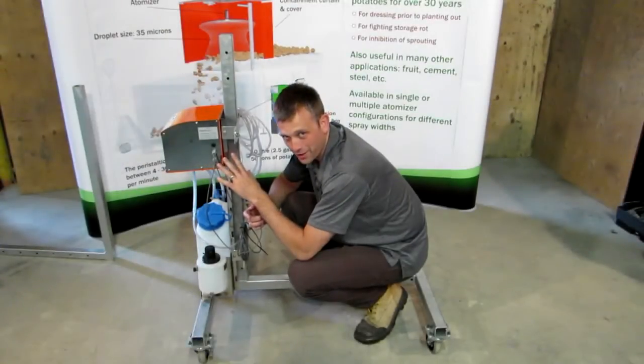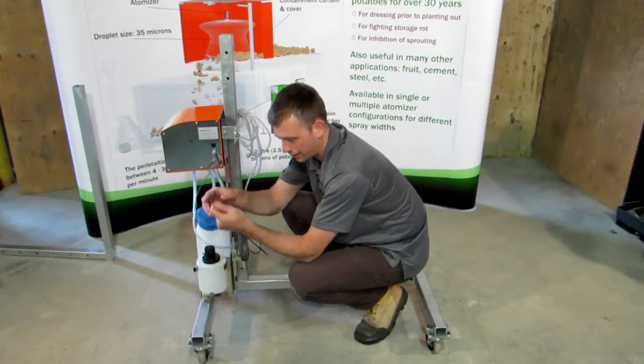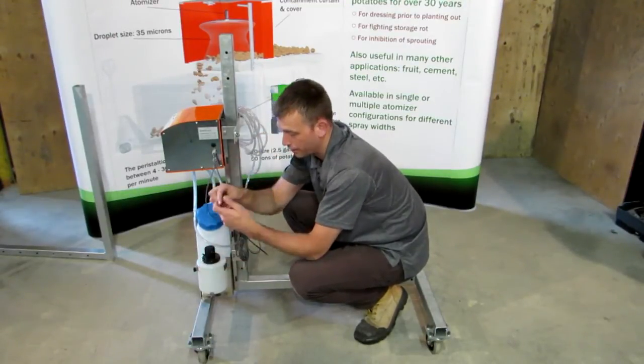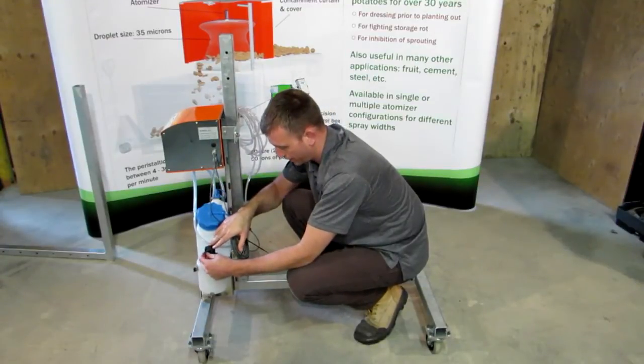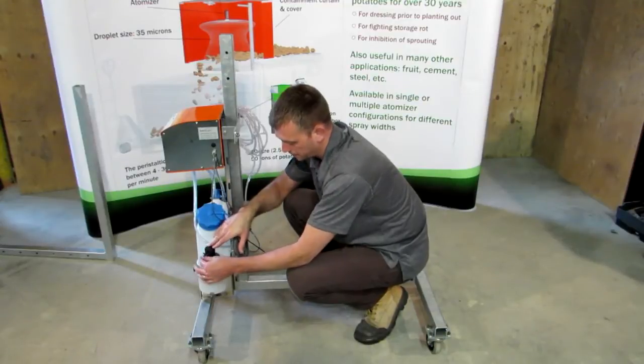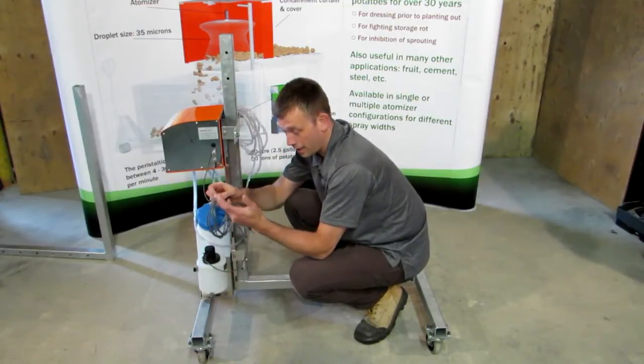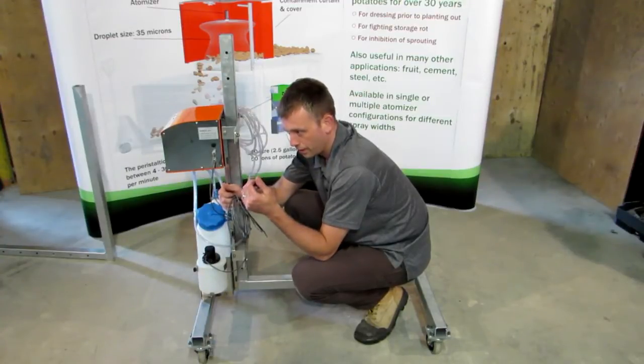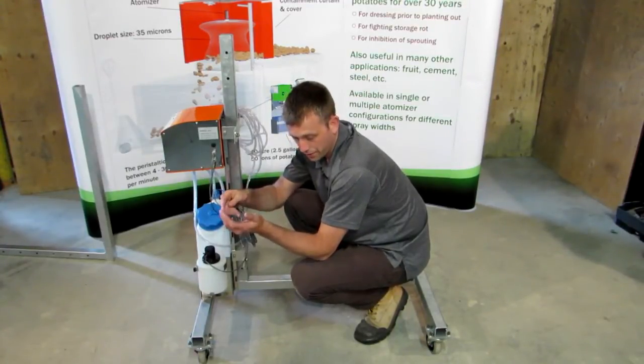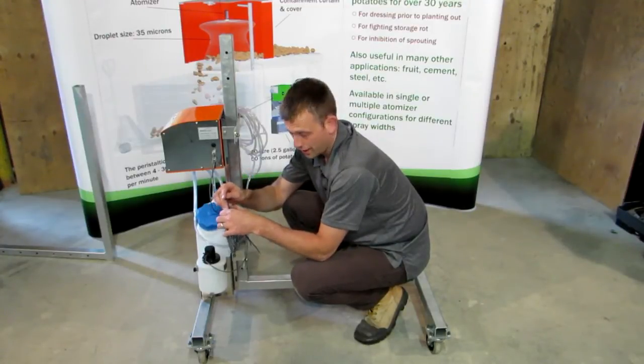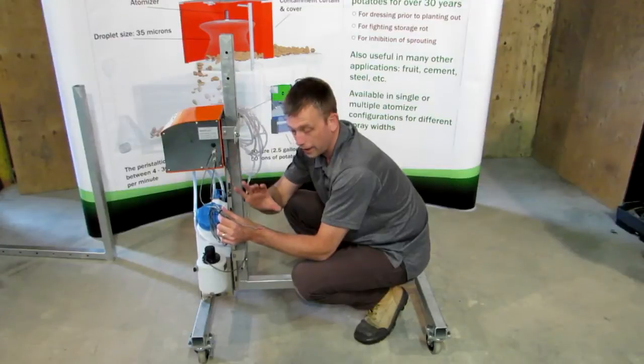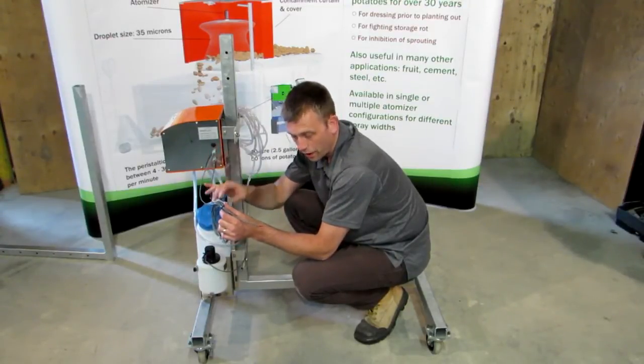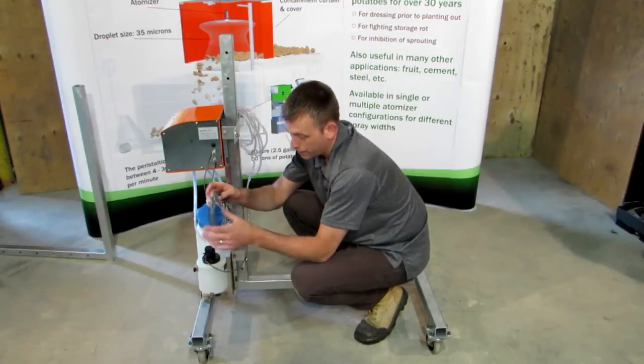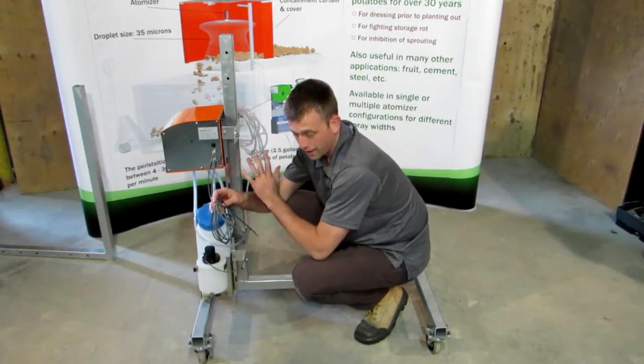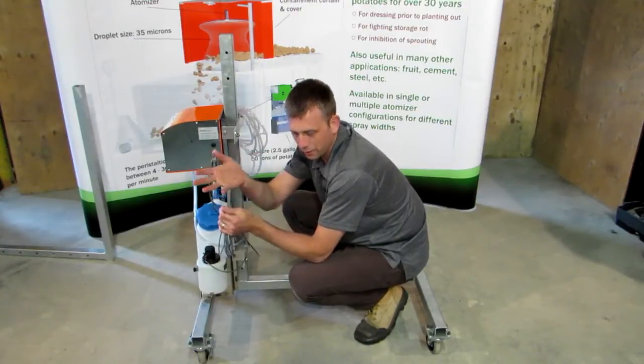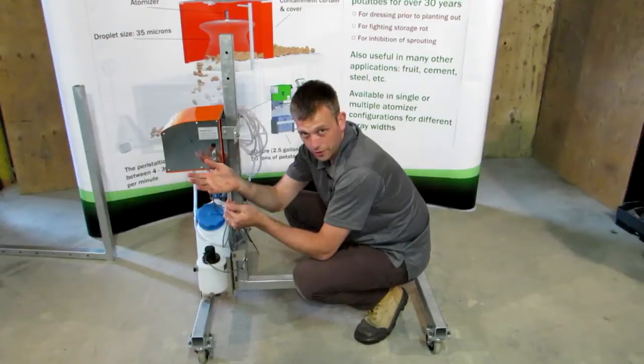There are 2 wires coming out of the side of the pump box. The bottom one has the flat connectors on here to connect to our flushing pump. Be sure to match up the positive and negative correctly, and they just slide on there. The second wire has bare ends on it, and this is used if we're going to take advantage of the relay system to tie it into the table, for example. We'll go into the details of that a little bit, but basically the relay can accept any signal between 12 and 240 volts, AC or DC. We have to change one setting inside the pump box to use this. Normally speaking, we would put an AC plug on here and plug it into the table.